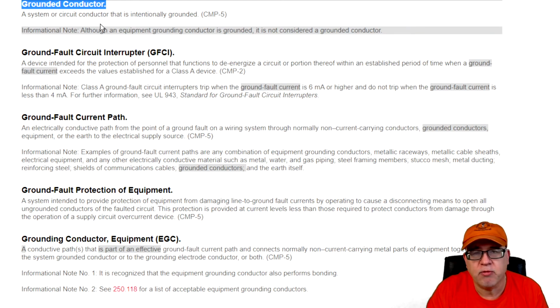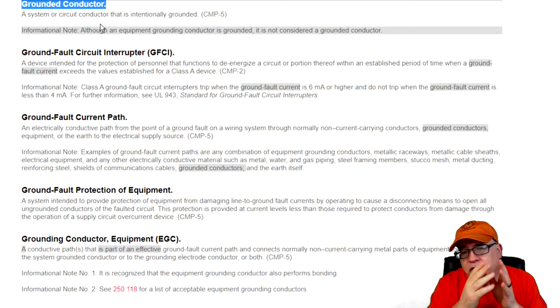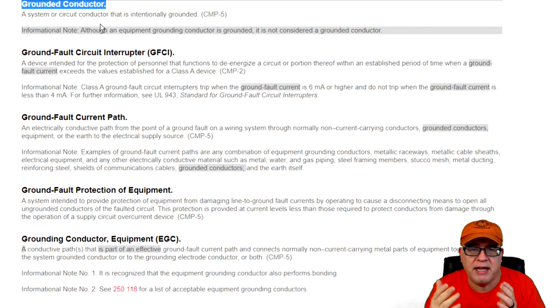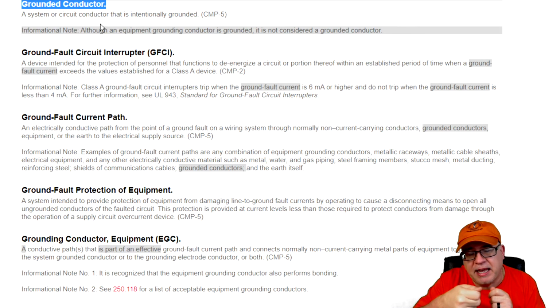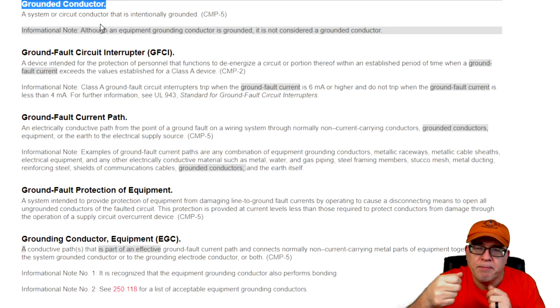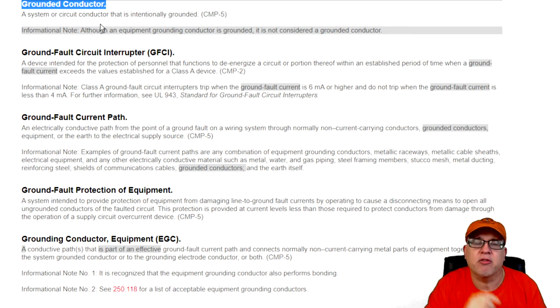On a transformer, for your typical house, you have 120/240 volts coming down off the transformer secondary. You typically have the bare neutral coming down, and the reason it's neutral is because you have two legs and the measurements are the same between each phase, A and B, or line one and line two, to the neutral. It's 120 from any leg to neutral, and between the legs it's 240. That is a neutral. Back at the transformer, it is intentionally connected from that conductor to the earth, so it is considered a grounded conductor.